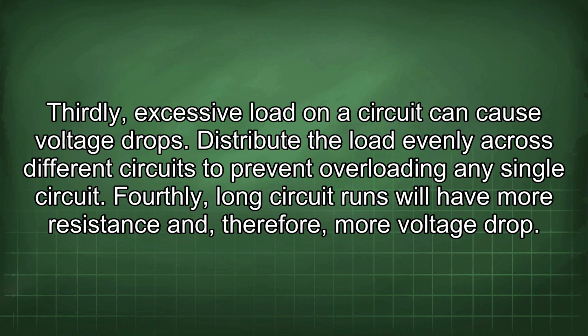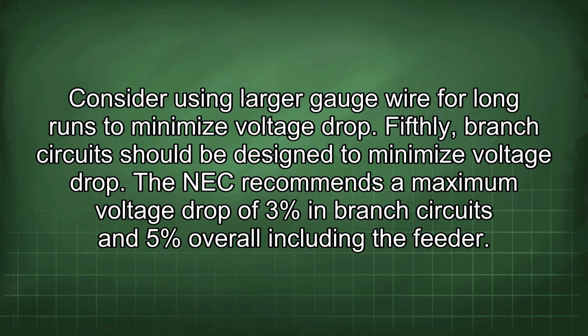Thirdly, excessive load on a circuit can cause voltage drops. Distribute the load evenly across different circuits to prevent overloading any single circuit. Fourthly, long circuit runs will have more resistance and therefore more voltage drop. Consider using larger gauge wire for long runs to minimize voltage drop. Fifthly, branch circuits should be designed to minimize voltage drop. The NEC recommends a maximum voltage drop of 3% in branch circuits and 5% overall, including the feeder.